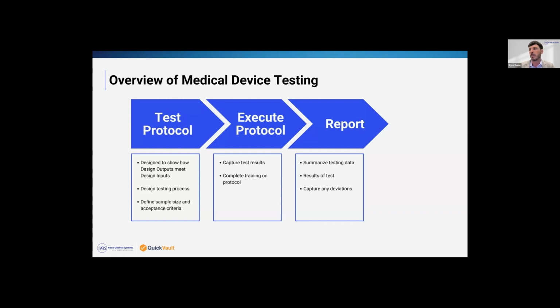You want to define the sample size and acceptance criteria of the testing. So both of these things are pretty critical for your testing to make sure that you define these properly. Acceptance criteria is how do you know that your test is going to pass or fail? So you need to define that in your protocol before you start testing. If you start testing and you don't have defined acceptance criteria, then you can just say after the fact, oh yeah, that passed, we're good to go, right? So you have to define your acceptance criteria before you start testing to make sure that your product and test actually is relevant to what you're trying to do. And then the sample size will determine how many tests you have to complete and what percentage have to pass for you to meet the requirements of this protocol.